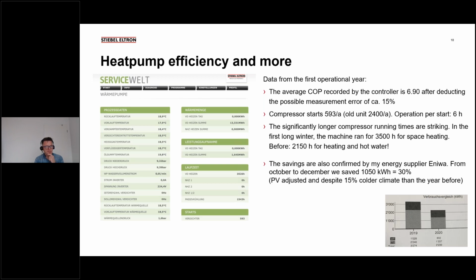The savings in energy — I measure 3 things. I measure it on the heat pump controller, which is not super accurate, to be honest, but I also have a Shelly EM energy meter that measures the consumption of the compressor, the pumps, and everything. I found out that it's using 30% less energy than before with the old heat pump. I also got a nice confirmation from my energy supplier, where you also see those 30% in savings.